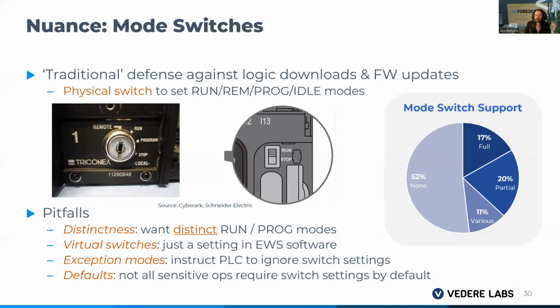Secondly, you want to avoid having a virtual switch setting in the engineering software, where sometimes you have a physical mode switch, but in the engineering software, you can override it. You can just take engineering actions. You can say, go to run mode, go to program mode, and that overrides whatever is happening in the mode switch on the PLC. You don't want any functionality like that. Third, you should be aware of exception modes, which configure the PLC to ignore the switch settings. And finally, some PLCs are not configured to require these switch checks prior to engineering operations by default. You need to explicitly enable that. So be aware of that as well.